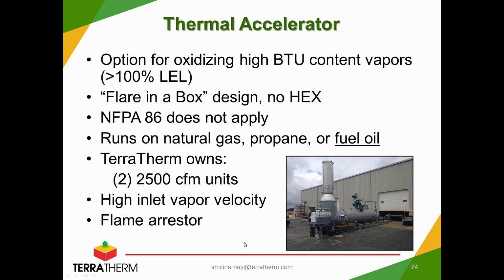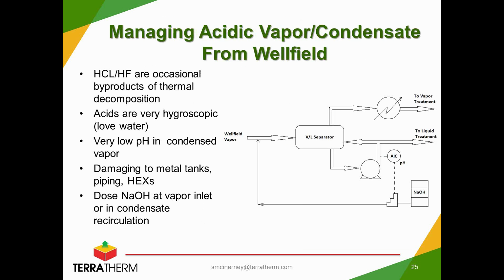Capacity, again, the 2 units are about 2,500 CFM each. And the way that these things are operated safely is that there's a very narrow throat leading into the oxidizer, and we maintain very high inlet vapor velocities feeding the unit, so there's no risk of backflash. And we absolutely couple that with flame arresters and other instrumentation to make sure that it's operating in the safe operations range.